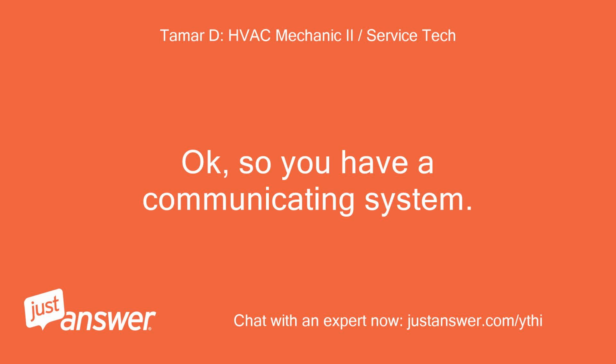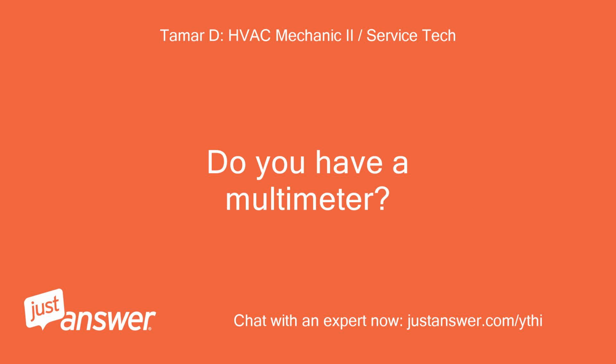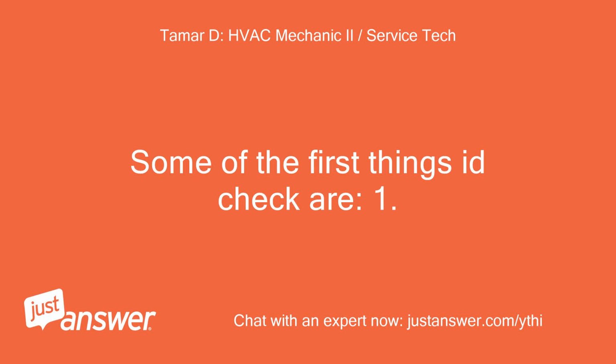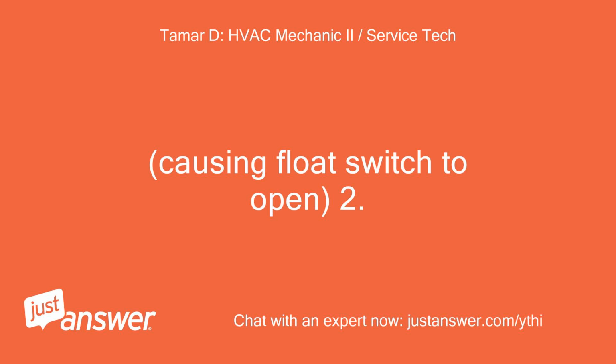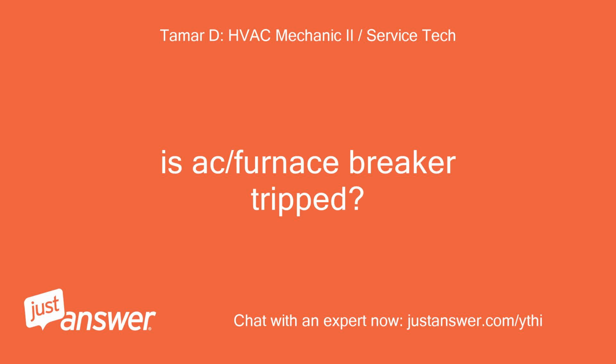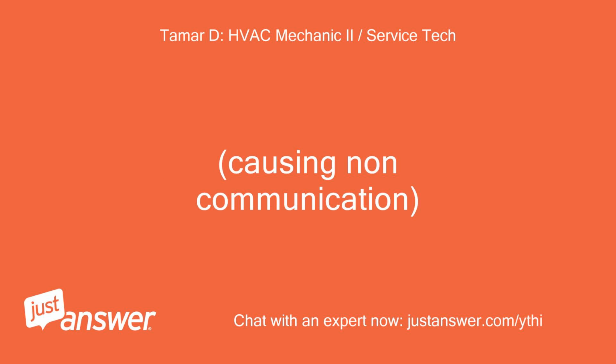Okay, so you have a communicating system. Do you have a multimeter? Some of the first things to check are: 1. Is the furnace/AC drain blocked, causing the float switch to open? 2. Is the AC/furnace breaker tripped, causing non-communication?